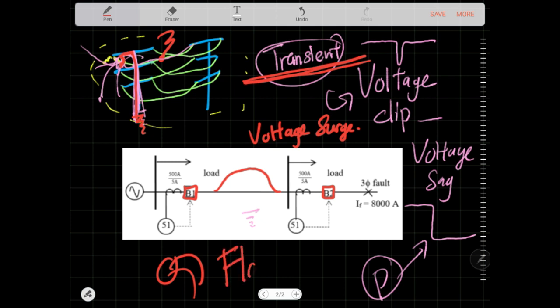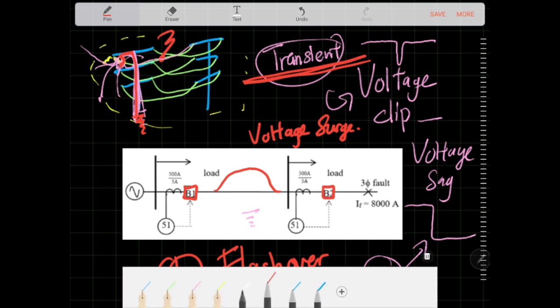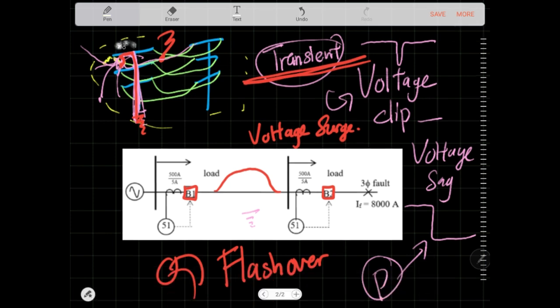When a flashover happens, the ions in the air get energized. Normally air is insulating, preventing current from jumping over, but once the air is ionized it becomes much easier to conduct. So even after the voltage surge drops, the ionized air allows current to continue conducting from the line to a surface and straight to ground — and therefore the fault still exists.